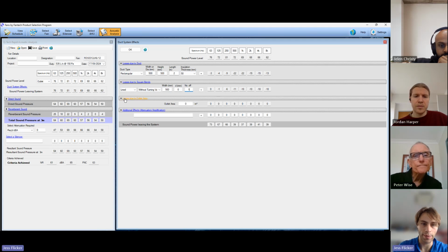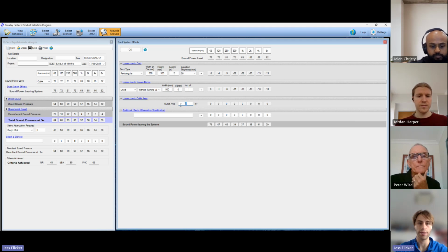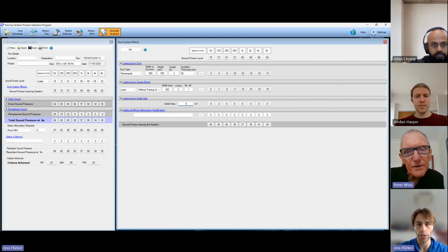And then, depending on your outlet area - the larger your outlet area is, I believe the air velocity will be lower, so then you get more attenuation. So sometimes you'll see a transition at the end, like a kind of bell on the end of the duct, which brings the velocity down when the air is supplied into the space. So you can model that - it's what your outlet area basically is, the neck size of the grill.